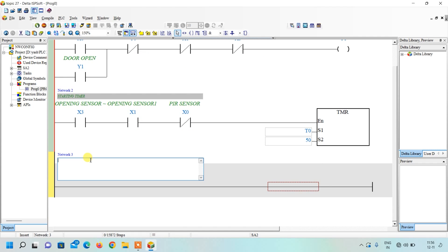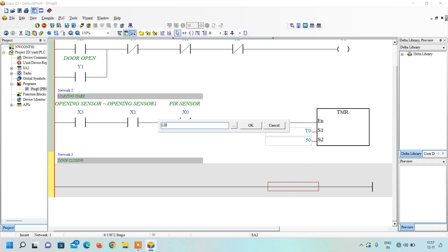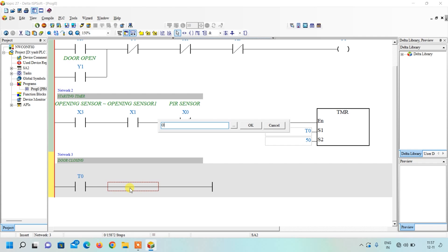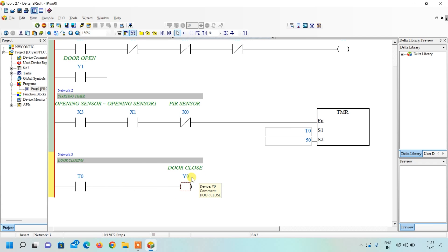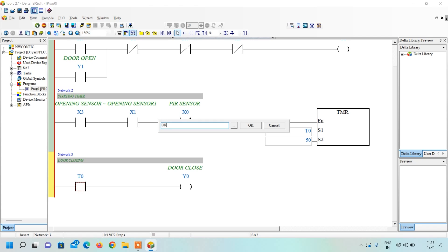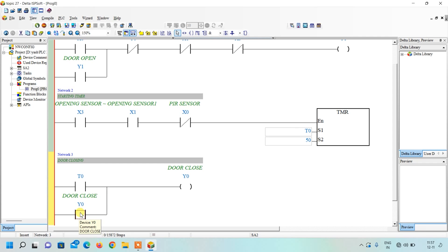Insert a new network — this is the network for door closing. When the timing is completed, output Y0 should turn on to close the door. Write LD T0 to insert the NO contact of T0, then write OUT Y0 — the door close sequence output turns on. We must latch this: select Y0 parallel to T0 and write OR Y0, so even if T0 turns off, Y0 stays on. Again, use interlocking with the NC contact of Y1 — if the door opening output is currently on, Y0 cannot turn on.